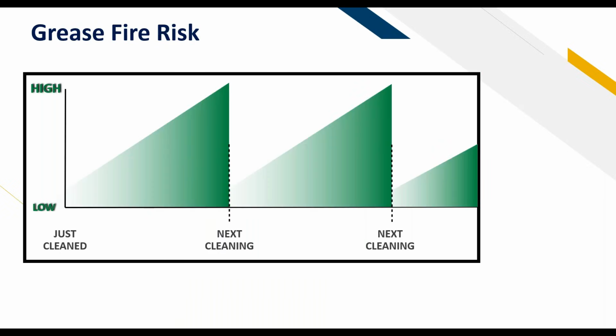And here's just an example of what we're looking at with grease fire risk. This can apply to PCUs. This applies to grease duct. But for right now, we're going to be looking at the grease duct. There are scheduled cleanings that these restaurants need to have, and typically these cleaning companies will come in the middle of the night and they will have to clean the system of grease. They'll get up into the duct, they'll open up all the clean outs, and they'll clean it up as much as possible. It's a pretty nitty-gritty job, and they have quite some difficulty keeping staff to do that work for them. As you can see, when you've just cleaned it, there's very low risk for grease, but as you get closer to your scheduled cleanings, that risk does go up.